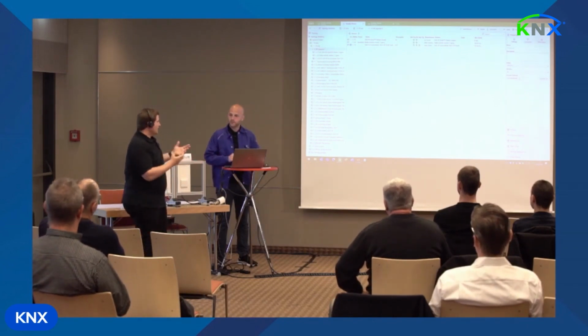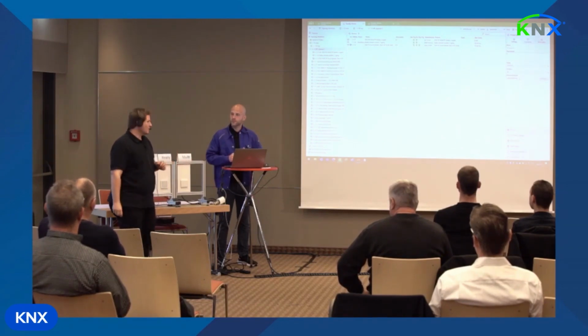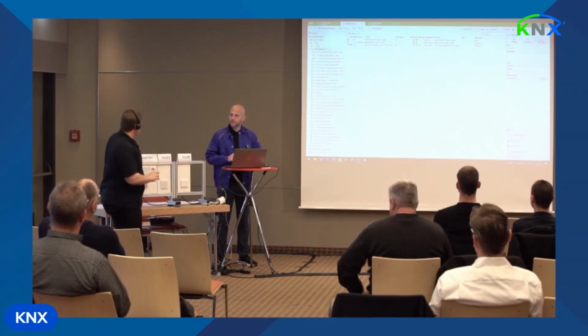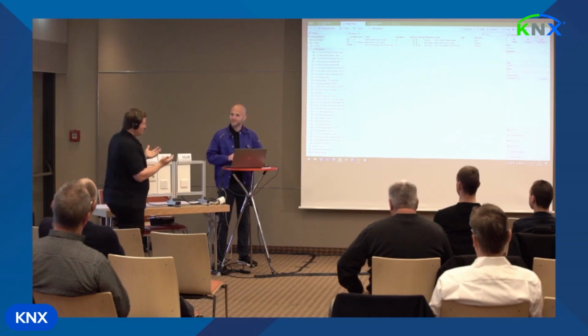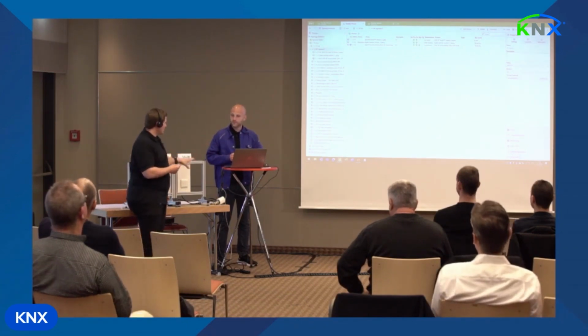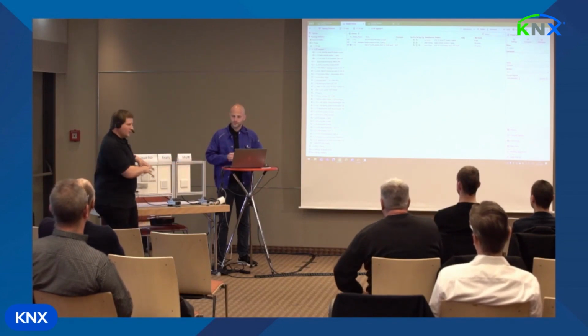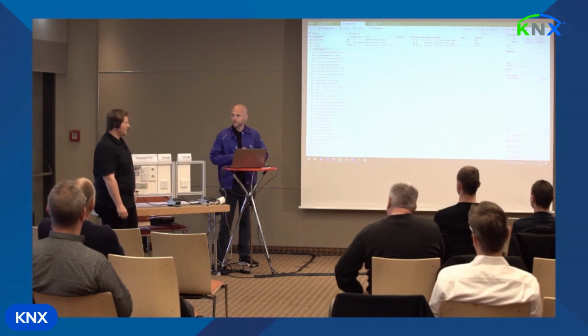And for this, the domain address separates these different RF lines and segments, and we move the devices from the former line into this new segment. And just to minimize possible things which could go wrong, we make sure that in this new segment we use the same domain address that we formerly used in the line. Okay, so just for presentation purposes, normally you should not care about the domain address.